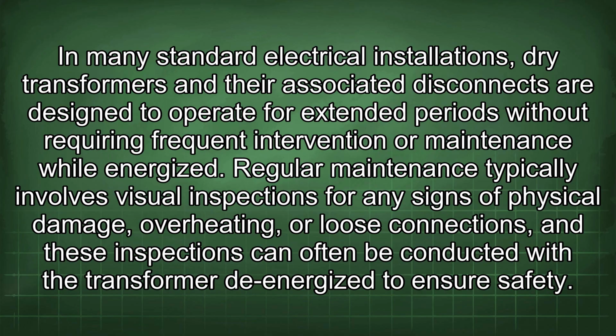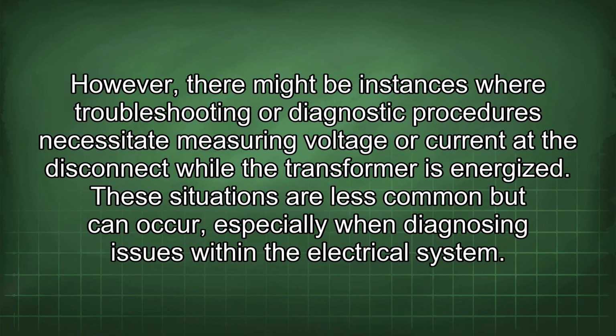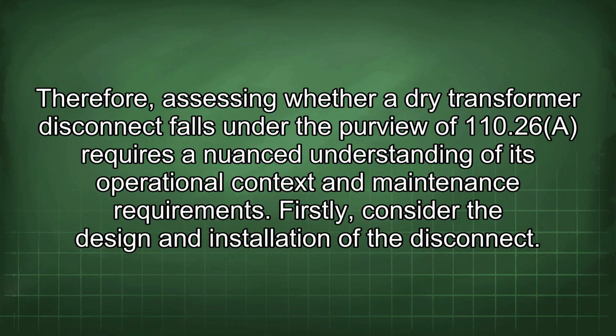Regular maintenance typically involves visual inspections for any signs of physical damage, overheating, or loose connections, and these inspections can often be conducted with the transformer de-energized to ensure safety. However, there might be instances where troubleshooting or diagnostic procedures necessitate measuring voltage or current at the disconnect while the transformer is energized. These situations are less common but can occur, especially when diagnosing issues within the electrical system.